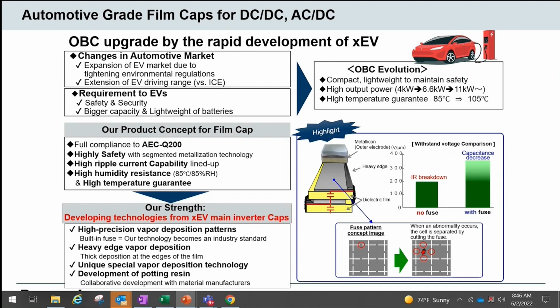If you look at the slide on the lower right-hand side, you'll see an overview of the capacitors as they exist with the metallization and the dielectric film. The interesting part is the fuse pattern: if you have a fault in the dielectric where you have a short circuit, the current will burn those fuses out, eliminating that segment from the capacitor. This lowers the capacitance a tiny bit, but gives you overall the same capacitance at the same voltage, and a longer lifetime in specific applications.